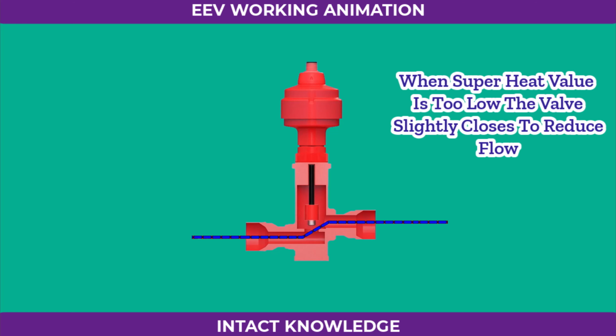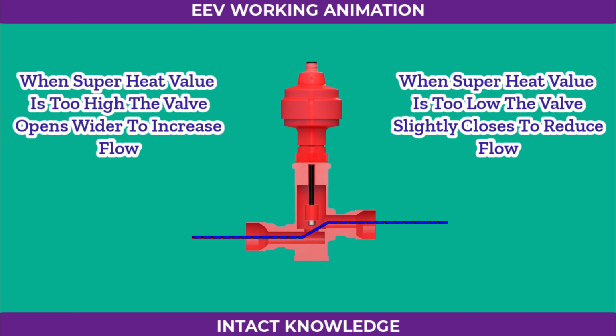When the superheat value is too low, the valve slightly closes to reduce flow. When it's too high, the valve opens wider to allow more refrigerant in. This process ensures maximum evaporator efficiency and prevents liquid refrigerant from flowing back to the compressor.